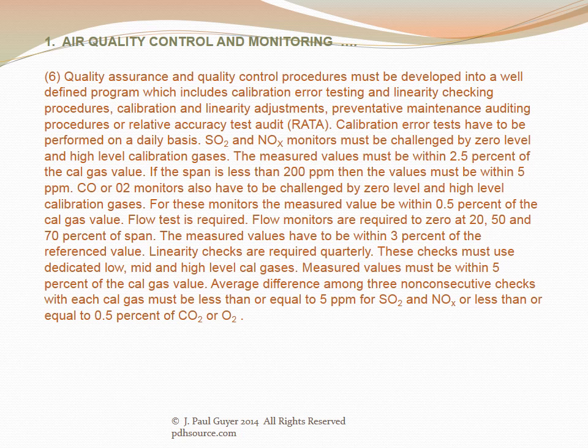Carbon monoxide or O2 gas monitors also have to be challenged by zero level and high level calibration gases; the measured value must be within 0.5 percent of the cal gas value. Flow monitors are required to zero at 20, 50, and 70 percent of span, with measured values within three percent of the reference value. Linearity checks are required quarterly using dedicated low, mid, and high level cal gases; measured values must be within five percent of the cal gas value. The average difference between three non-consecutive checks with each cal gas must be ≤5 ppm for SO2 and NOx, or ≤0.5 percent for CO2 or O2.